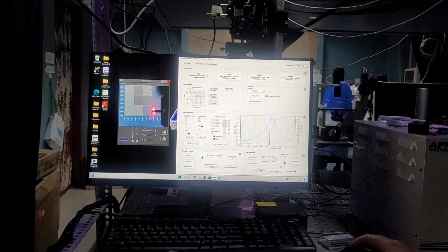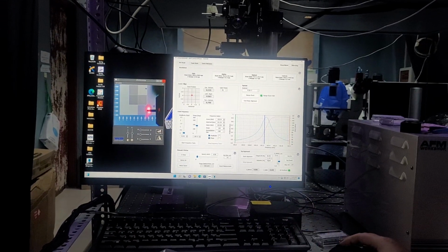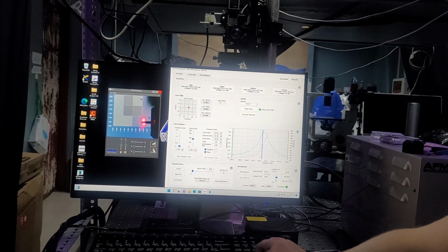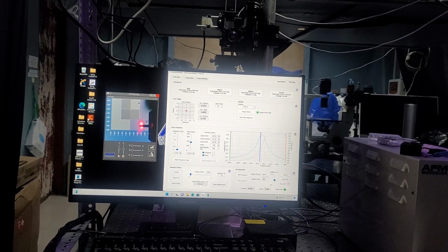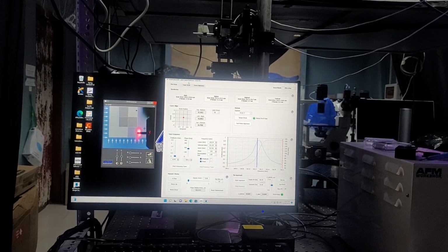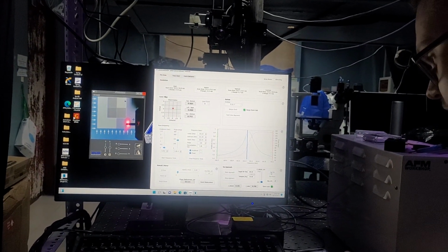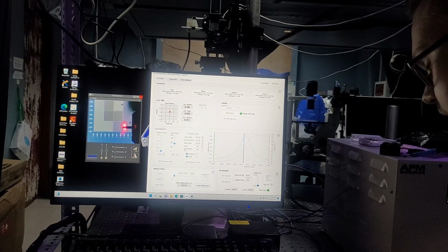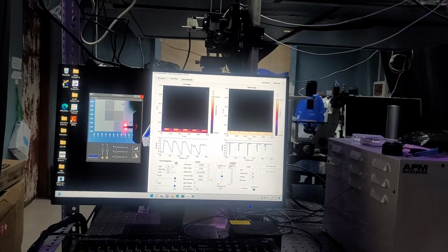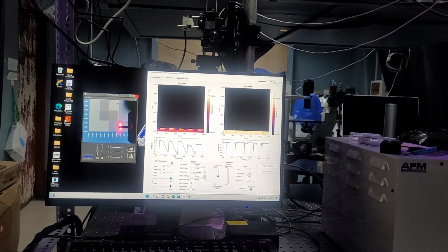Okay, here we go, we're back on the surface. So I'll go ahead and check, say from 80 to 79, it moved. 79 to 78, it moved. From 78 to 77, it did not move, so I'll move 1 to 3% below that, so I'll just go to 76. Then you'll want to check your position, make sure that you're about halfway. In this case, I'm a little bit under. So I will just jog a couple of times, and we're right near the middle. It does not have to be perfect, you just want it to be near that middle, both for the flexibility and for accuracy.